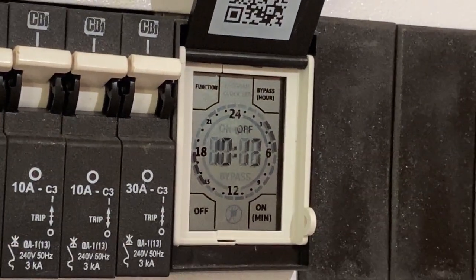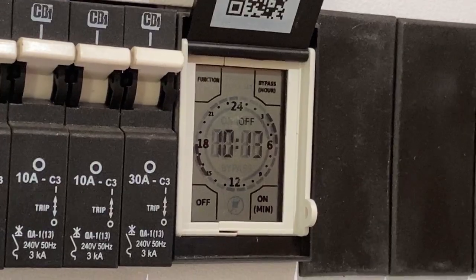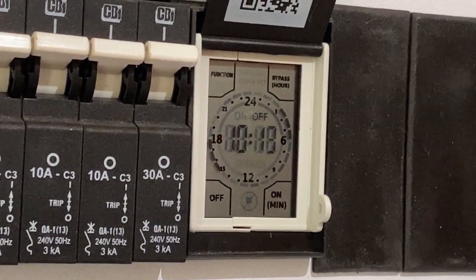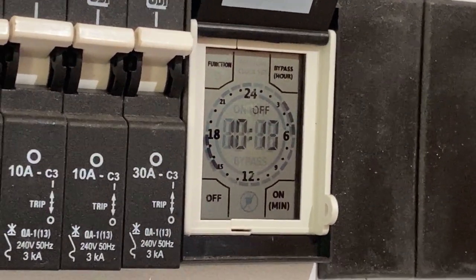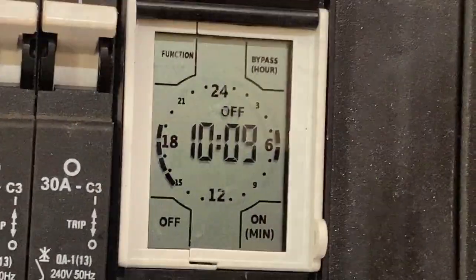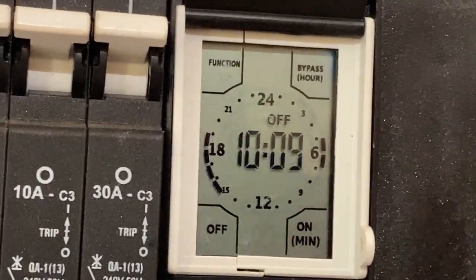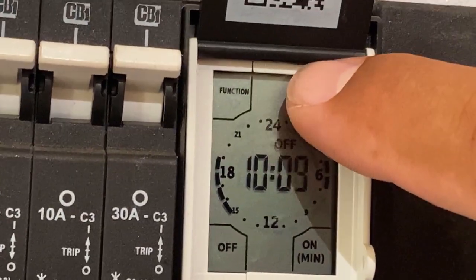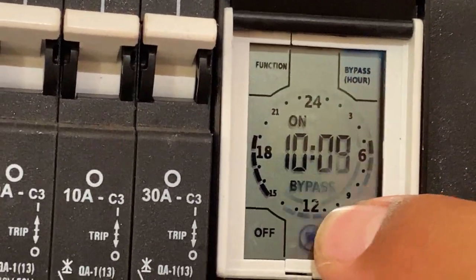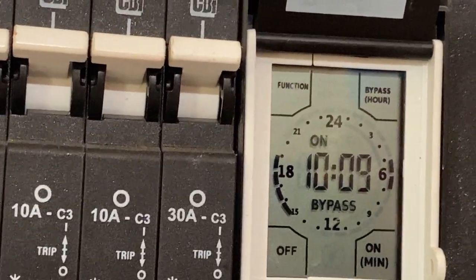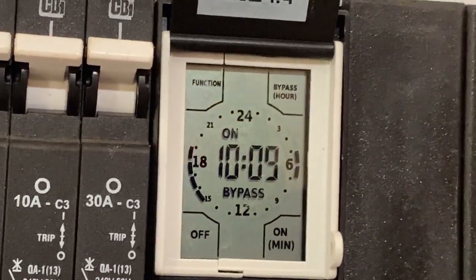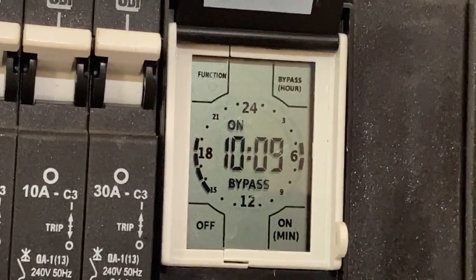It indicates that your contact is off, which means your geyser element is off. If you want to bypass it manually, you press the bypass button on the top here, hold it in for two seconds, then it flashes. Then you press the on button and you can hear a clicking sound on the relay which indicates that the relay is clicked in and your geyser is actually switched on manually.